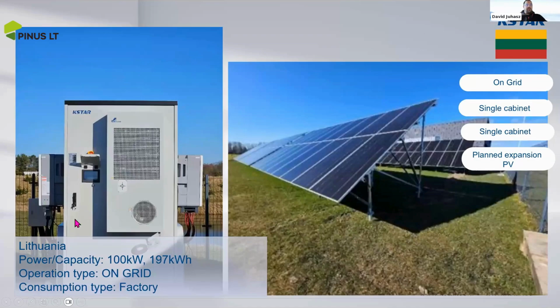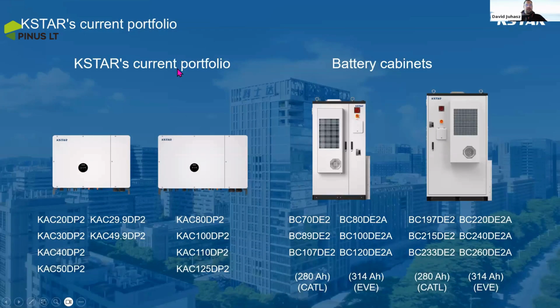And we have one project in Lithuania, and this is a simple single cabinet with solar extension, mostly working in on-grid mode. The portfolio of our system, as I mentioned, has different versions of the nominal power of these hybrid inverters and different capacity for the storages. In our system, for the 280 ampere hour cell, we are using CATL cells, and for the 314 ampere hour cells, we use EVE.